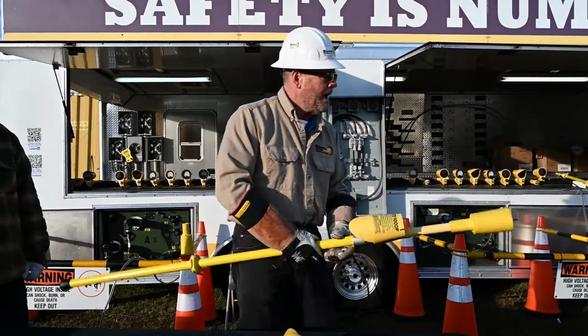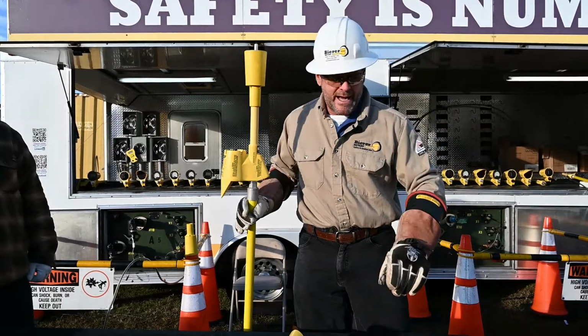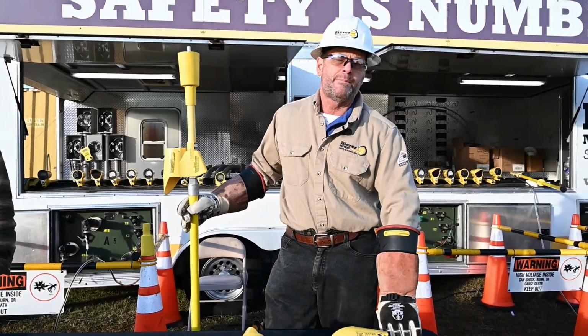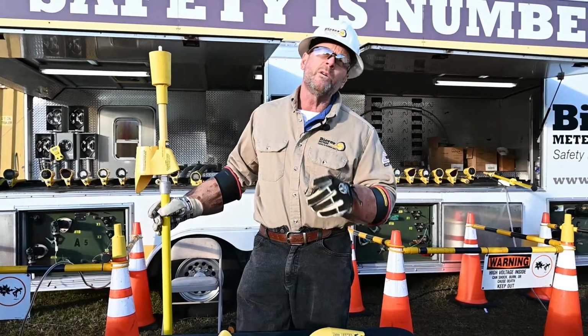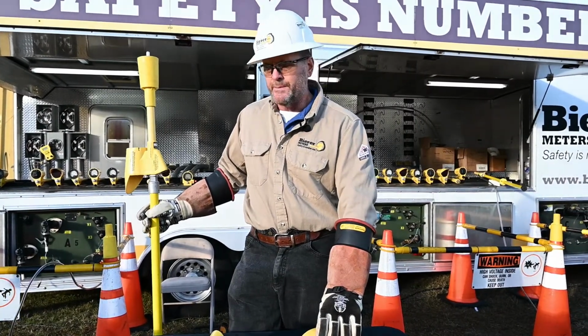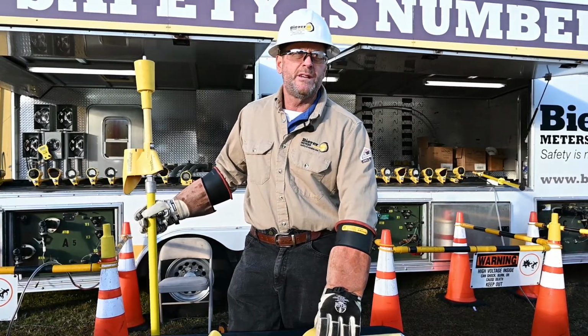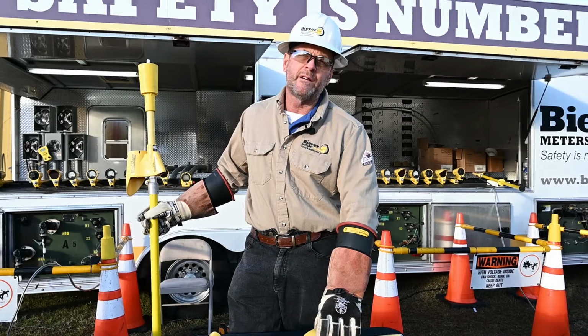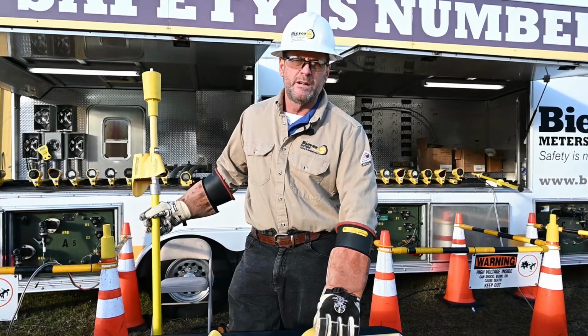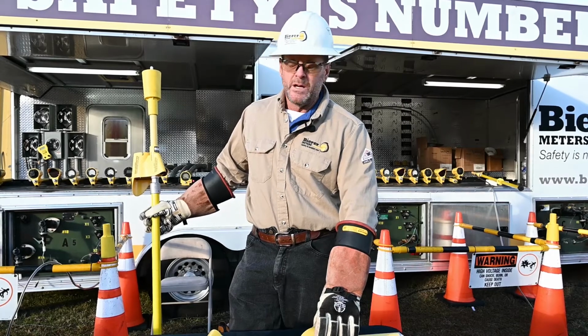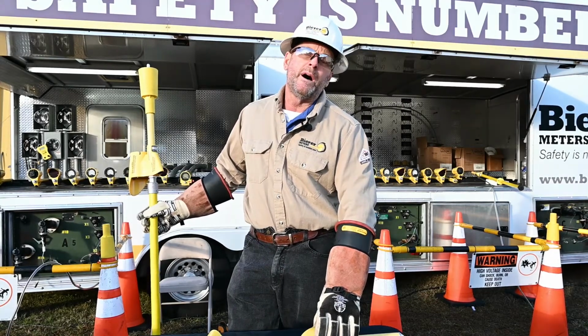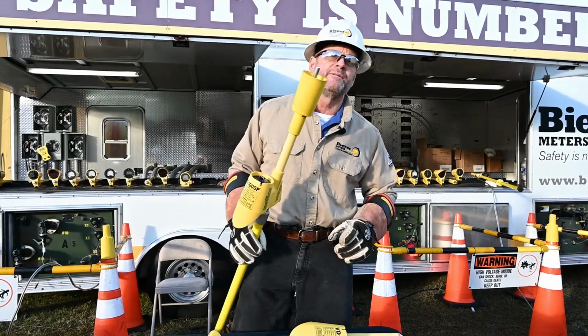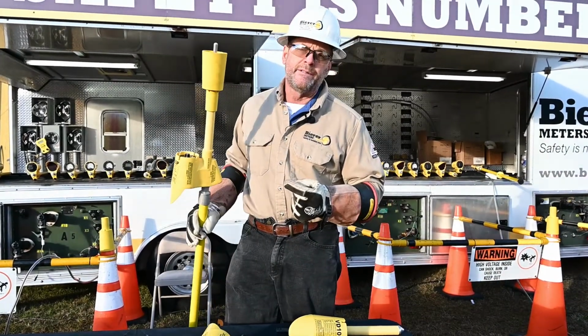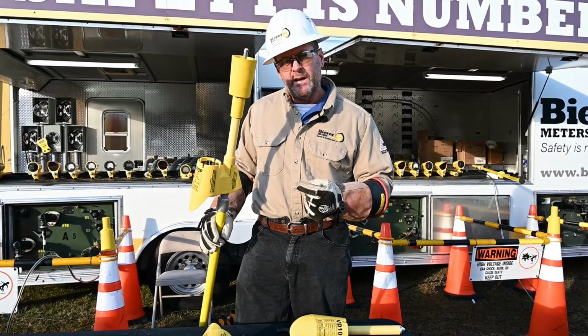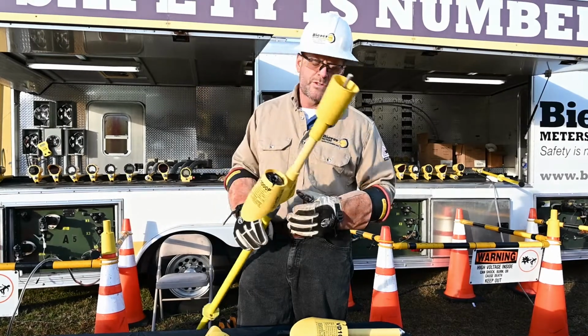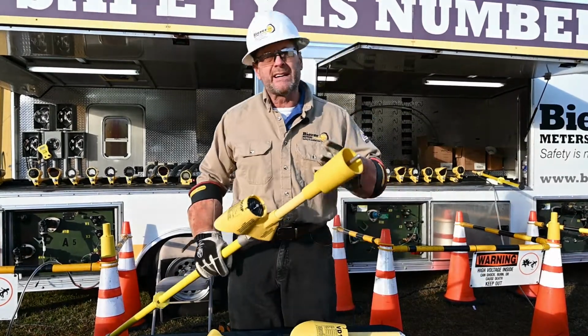So what we're going to do is go to 1910.269, lowercase n, where it talks about your temporary protective grounds. Go down to number 5. It talks about how, before installing your TPGs, the line worker must go ahead and verify an absence of nominal voltage, your system voltage, an absence. That's what we're looking for. But we like to train it as: we're going to look for an absence of nominal voltage, a lack of backfeed, and also an absence of induction. We have tools accurate enough to verify a lack of all three.